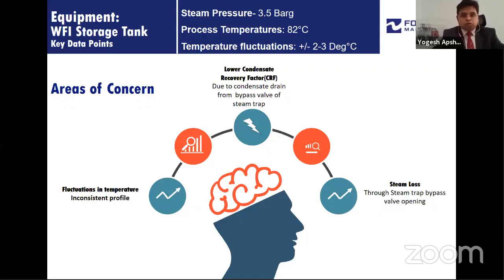Let's go to the next equipment, which is a WFI storage tank or a purified water storage tank. We have observed that 3 to 3.5 bar gauge pressure is given to the WFI storage tank, where we have to maintain a temperature of more than 82 or 85 degrees Celsius to avoid any microbial growth in the WFI. The WFI is always in circulation, even though it is stored in the storage tank, and the temperature to be maintained is always 82 degrees Celsius plus.